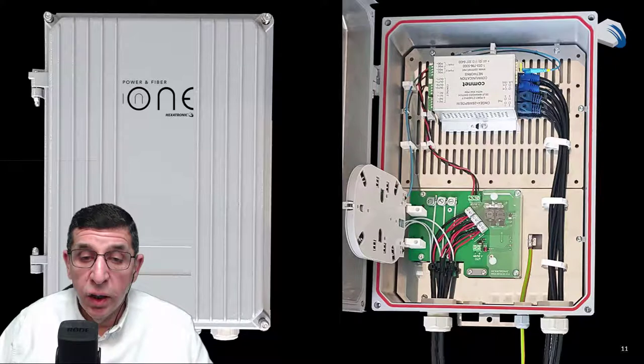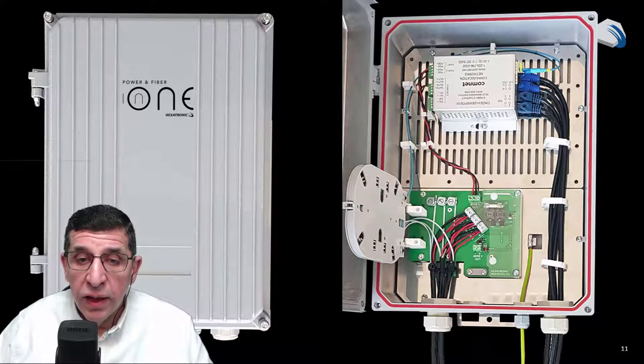That board is a voltage regulator. Let's say we started with 110 volts DC, by the time we reached this cabinet, it's 105 volt DC. So we don't need all of that to feed our switch. This voltage regulator will output 48 volt DC regulated, and that is the input that feeds the PoE switch.